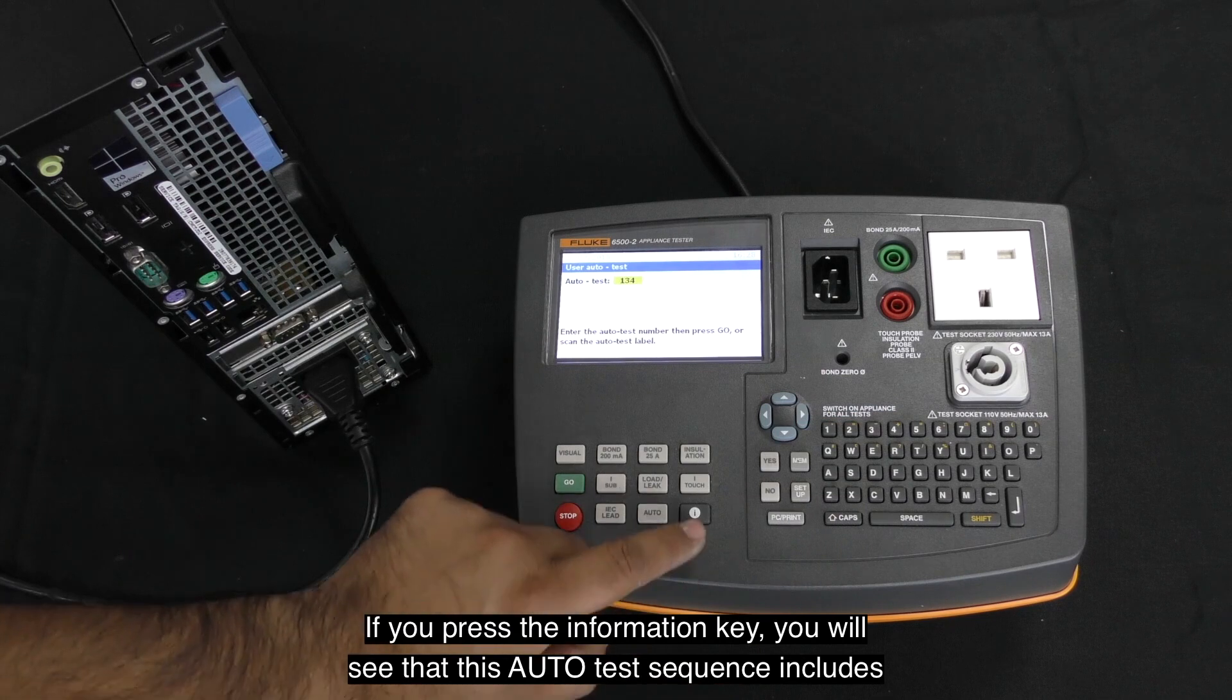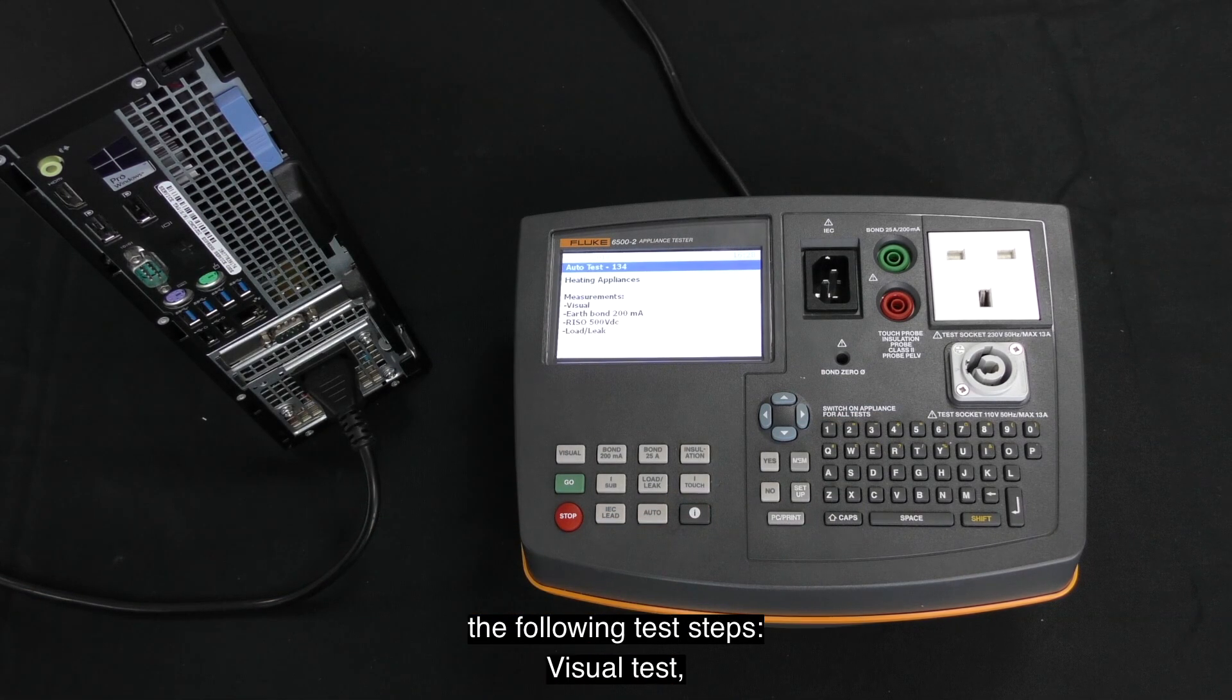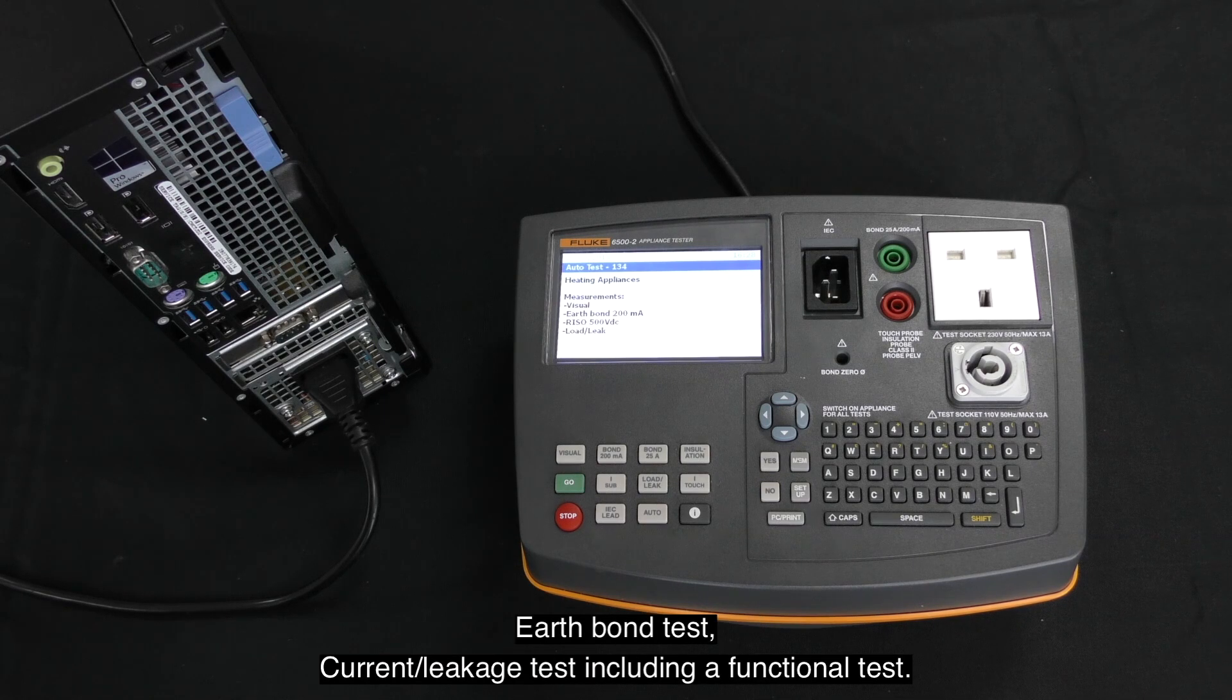If you press the information key, you will see that this auto test sequence includes the following test steps: visual test, earth bond test, current and leakage test, including a functional test.